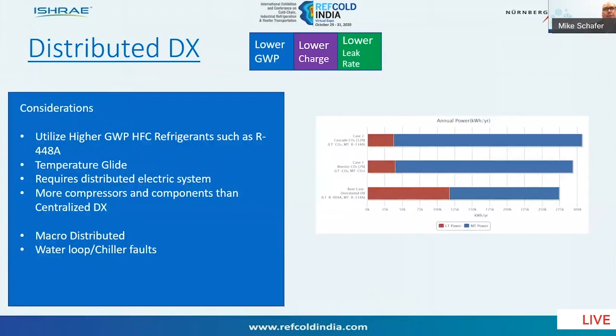So some of the considerations, typically these systems are going to use a little bit higher GWP refrigerant, such as a 448A. These types of refrigerant would have a more pronounced refrigerant glide. It's very manageable, but the evaporator or condenser circuiting may change. The other aspect, obviously with distributed, is you're distributing refrigeration equipment and by definition the electrical system as well. So that has to be taken into account in store design. And ultimately, there's going to be more compressors and components than a centralized DX.